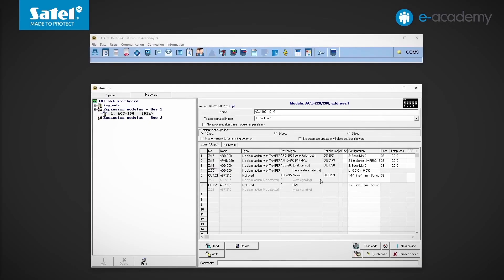We return to the detector settings. Three parameters can be set in the configuration field. The first one is the type of temperature threshold just discussed. The second parameter is the threshold temperature — here we can enter a value from the range of minus 30 to plus 70 degrees Celsius, with an accuracy of half a degree. The last, third parameter is tolerance, with a range of 0.5 to 10 degrees.